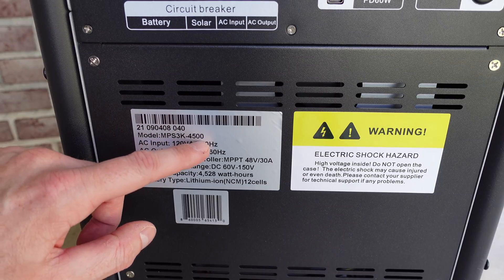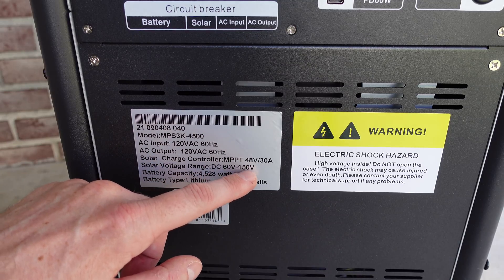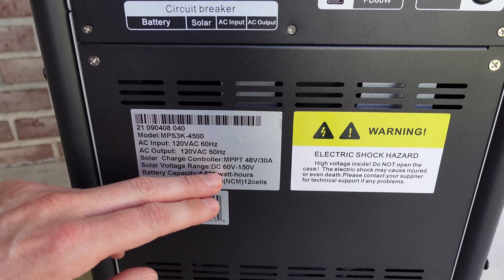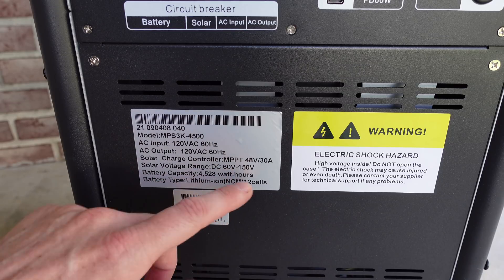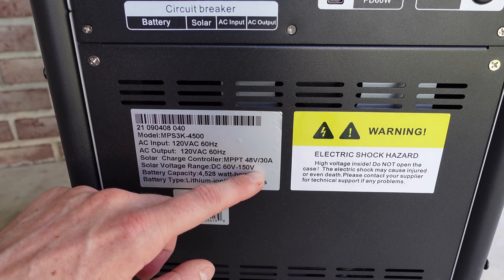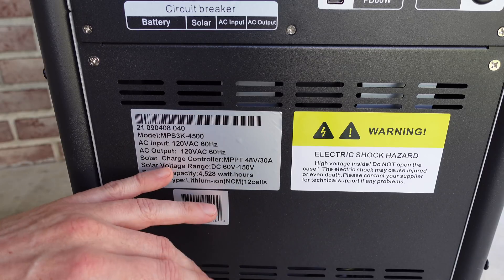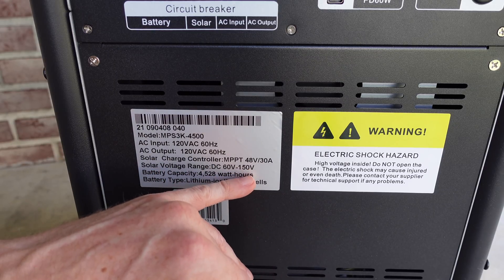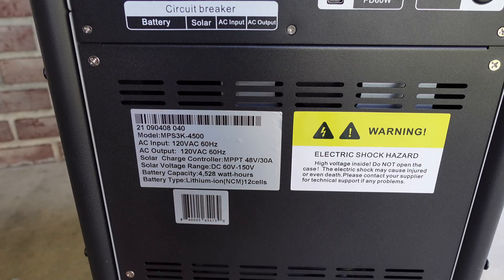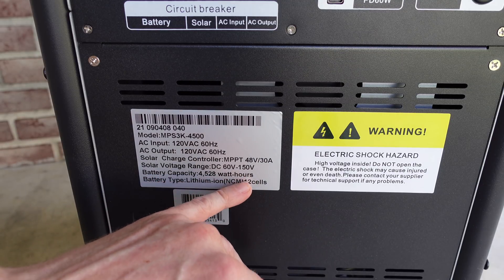On the left we have some specifications. Model number MPS 3K-4500. The solar input range is 60 to 150 volts. It doesn't specify if this is VOC open circuit or VMP operating voltage, but based on the 150 volt figure, I'm going to assume this is VOC open circuit. So you do not want your open circuit voltage to exceed 150 volts — I wouldn't even do 135 or 140. The exact battery capacity is 4,528 watt hours.